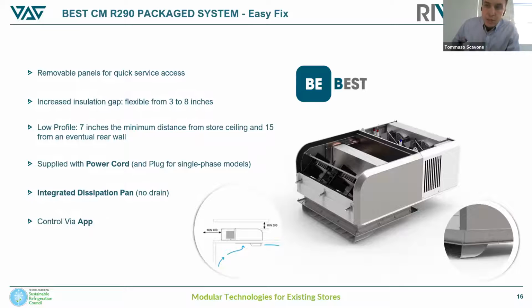The structure has been designed to guarantee easy access in case of service. The panels can be removed very quickly, and with a few simple operations, it's possible to access all of the main components of the circuit. The insulation gap predisposition for the walk-in panel thickness has been increased up to 8 inches from a minimum of 3, and it is adjustable, allowing flexibility of the same unit for all types of installations. So we know that the panel manufacturers now have increased the thickness of the panels to increase the efficiency of the walk-in itself, reducing the loads of the refrigeration system.